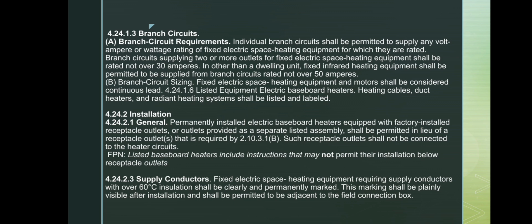Second, branch circuit sizing. All fixed electric space heating equipment and motors are treated as continuous load, meaning they must be sized for long duration operation. Listed equipment: electric baseboard heaters, heating cables, duct heaters, and radiant heating systems must be listed and labeled to ensure safety. Moving to section 4.24.2, installation.